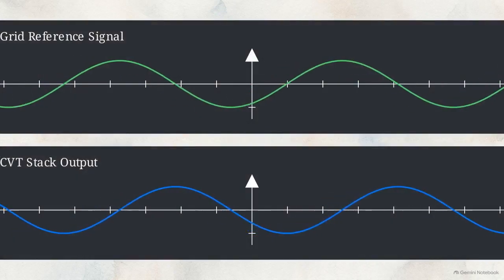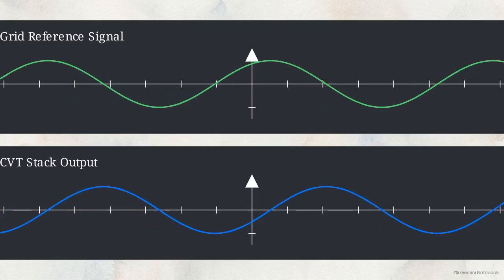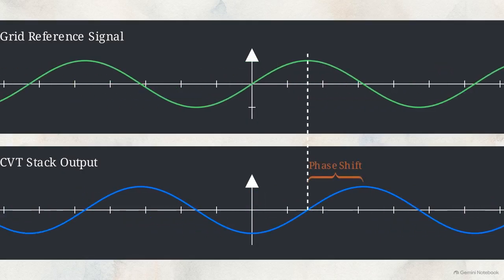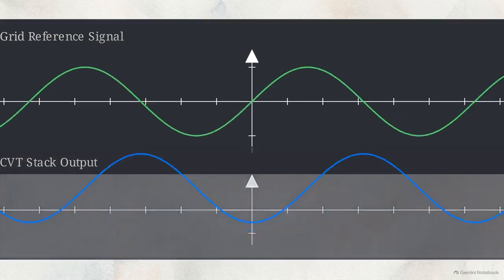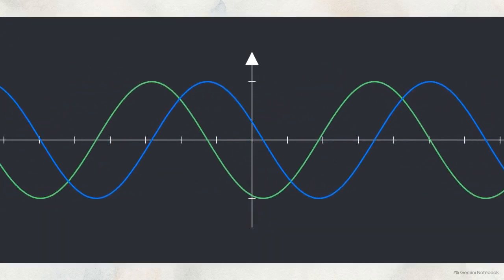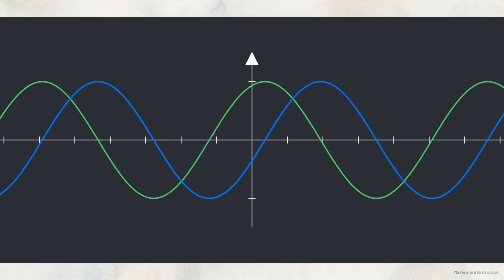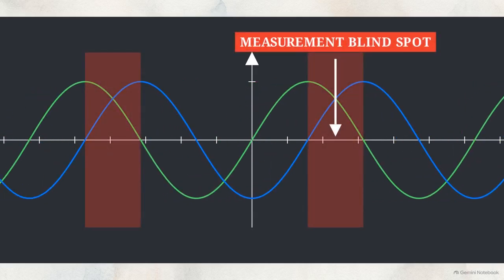However, routing current through the upper capacitor stacks introduces an electrical side effect. The capacitors force the AC signal's phase angle out of alignment. Protection relays calculate impedance based on strict phase timing. This phase shift introduces blind spots where grid operators cannot accurately detect a fault. To correct this, engineers install a specific compensator next to the transformer, the series reactor.